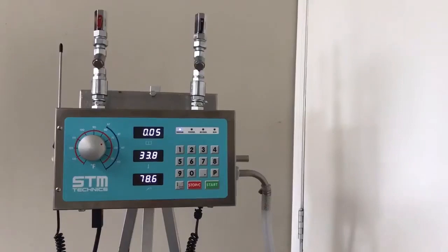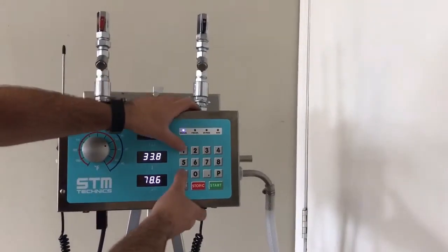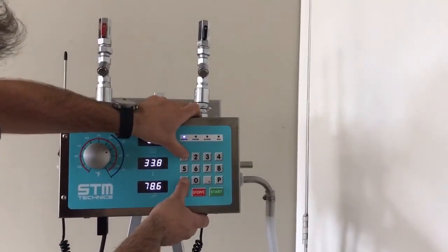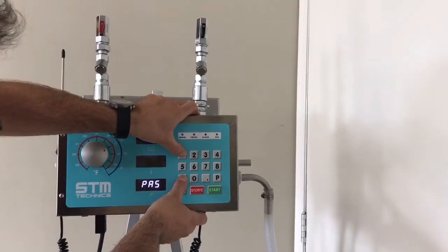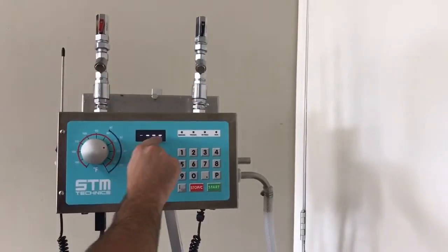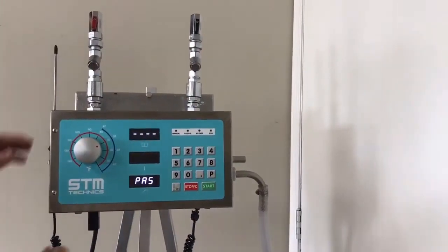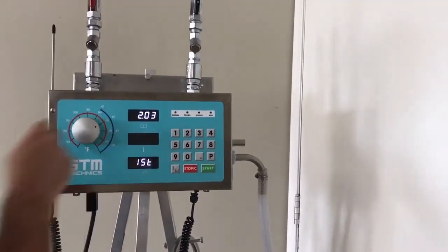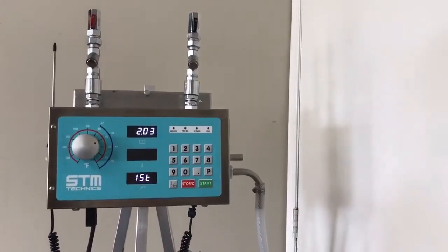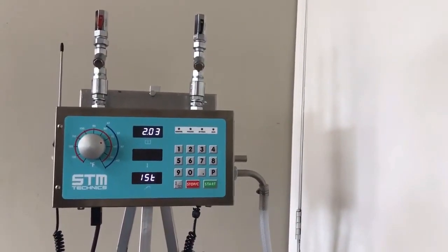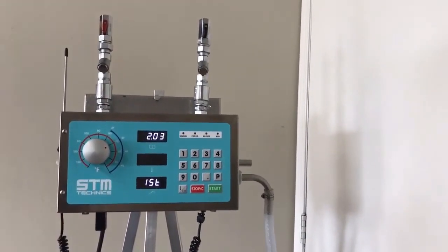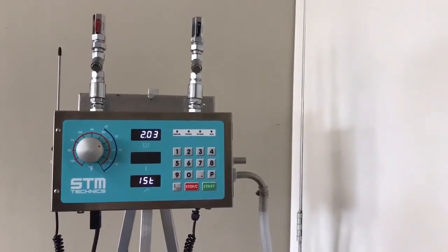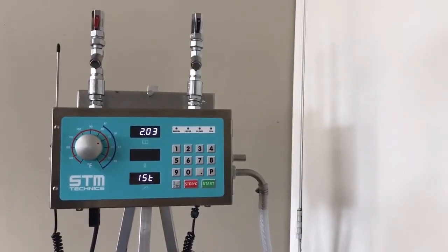First we're going to go into our internal parameters. To do so we press numbers one and nine together and hold. We have four dashes on the top. We punch in the code 1131 and we go into our first parameter window which is our tolerance. The unit comes from the factory set for a tolerance of two percent. You can reduce that to one percent.